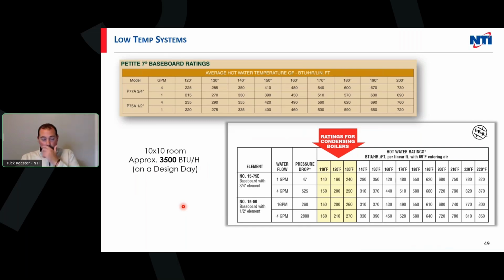I like using fin-tube as an example because it is a very popular heating emitter of choice for many contractors, and we oversize the daylights out of it on almost every installation. So I like to use this example when I'm talking to contractors, because I show them two different charts here. You can see average water temp, and then some manufacturers even call out ratings for the lower water temps of condensing boilers. So if I want that boiler to condense and be super efficient, I need to be in that water temp range, and that's average. So 130 average, that's 140 out, 120 back on a 20-degree delta. And then we got our GPM and all of that, and this is how many BTUs we put out per foot.